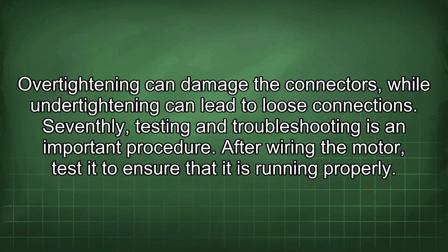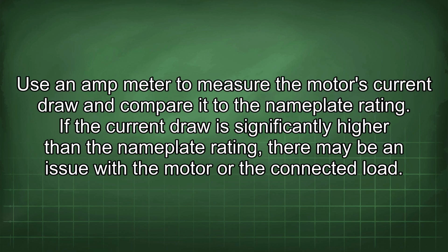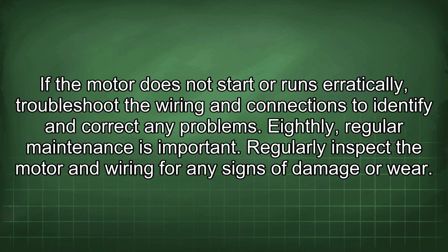Seventhly, testing and troubleshooting is an important procedure. After wiring the motor, test it to ensure that it is running properly. Use an amp meter to measure the motor's current draw and compare it to the nameplate rating. If the current draw is significantly higher than the nameplate rating, there may be an issue with the motor or the connected load. If the motor does not start or runs erratically, troubleshoot the wiring and connections to identify and correct any problems. Eighthly, regular maintenance is important.